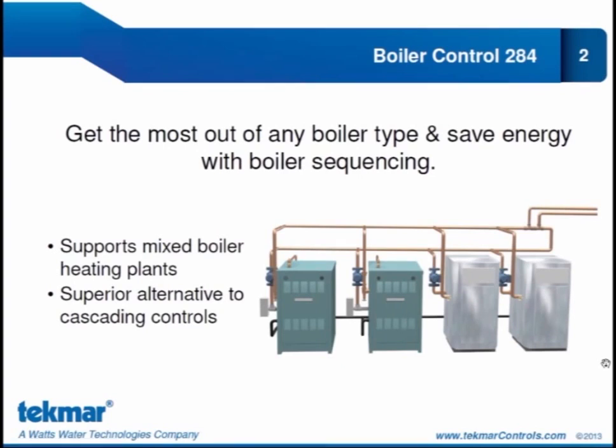The 284 addresses the present market and future growth of heating plants by supporting mixed boiler plant systems that include condensing and non-condensing boilers. Target markets are looking for the balance between high efficiencies and lower capital costs, and that balance can be achieved with a mixed boiler plant that includes condensing and non-condensing type boilers, if controlled with a sequencing algorithm that considers how efficiency varies with boiler type. And that is exactly what the 284 has been designed to do.